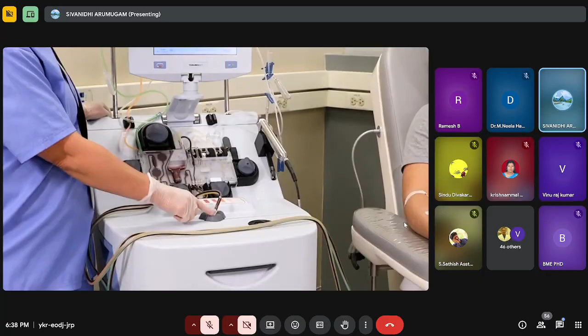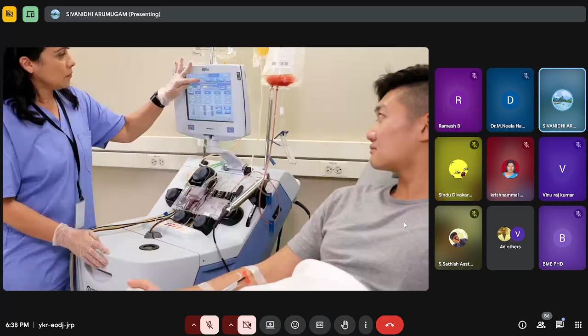The patient's blood is continuously pumped through the tubing set. The inlet pump draws the anticoagulated whole blood through the inlet line into the channel. Here you can see inside. We can't open it and see if the centrifuge is rotating at around 3000 RPM. So in the device we have an open space, we have optical resolution, and we have a camera to see what is actually happening inside.